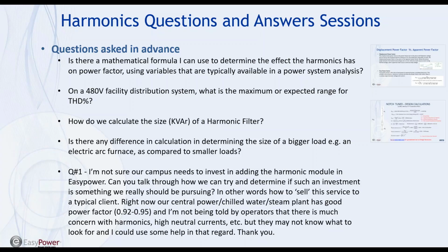So remember that the harmonic analysis software is used to evaluate harmonics within a facility, but more importantly, it's used as a tool to determine or predict what would happen if a change is made in the network. So the analysis tool, I would call this, is to evaluate what-ifs on a system, or to evaluate what might be causing problems on a system. So if you're not having problems on a system, it may not be something that you will be able to sell that easily. But if you are planning to make changes to any system, this is what this tool is used for, to evaluate what that change will be.